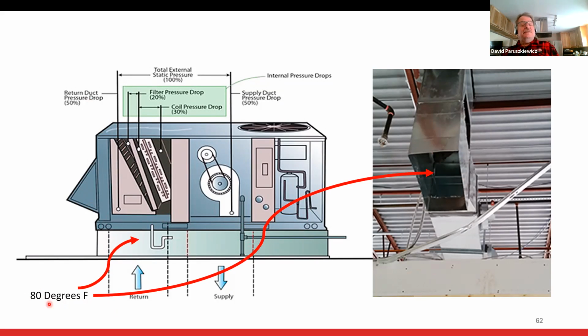Now, the one I always get is, well, the old unit didn't trip the limit and it did the same thing. Yeah, well, the old unit was 25 years old. The blower came on strictly on time and the limit would trip and reset and trip and reset and we'd cycle on the limit. Well, because of modern codes and energy requirements, these will lock out. If I have 4 consecutive limit trips, I'm going to lock this unit out. So we can't cycle on the limit anymore.